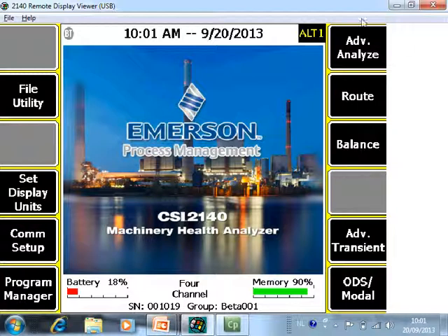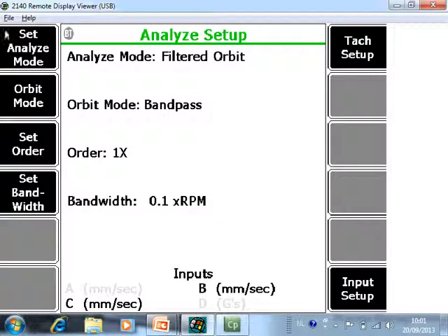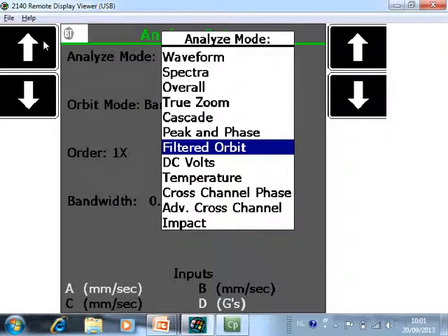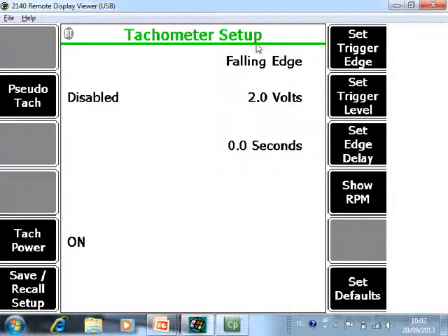First of all, go to Analyze F7, select Manual Analyze F1, go to Set Analyze Mode F1 and select from the list Filtered Orbit. In this case I will measure the orbit with a bandpass, one order and a bandwidth of 0.1 RPM.